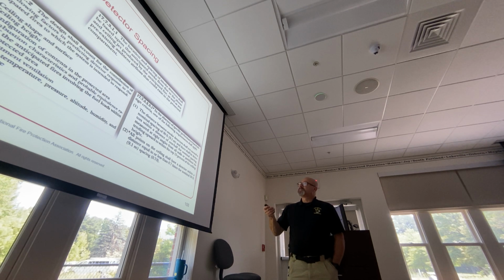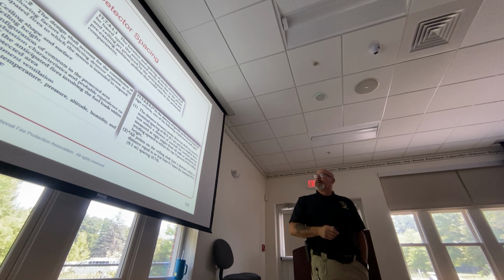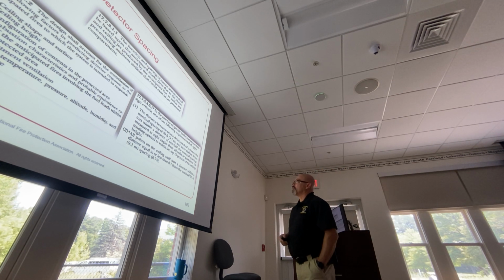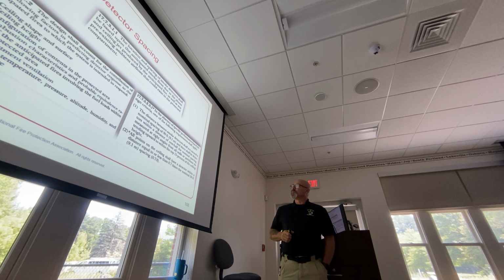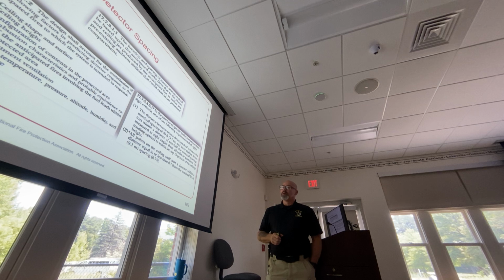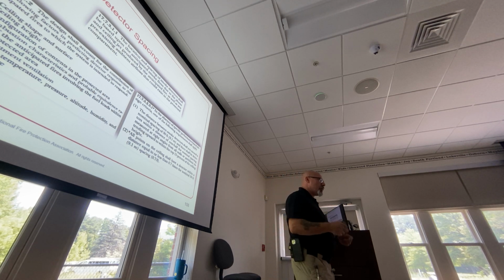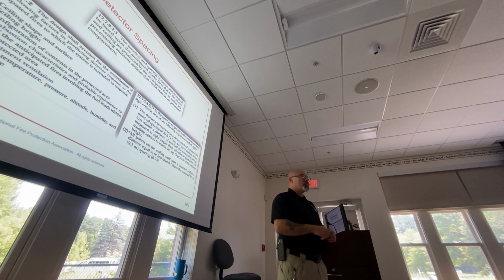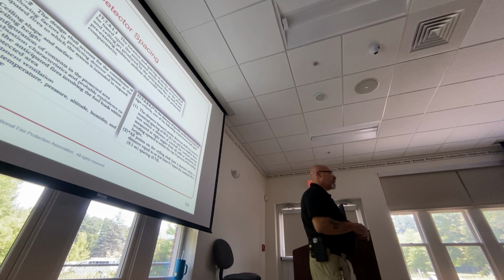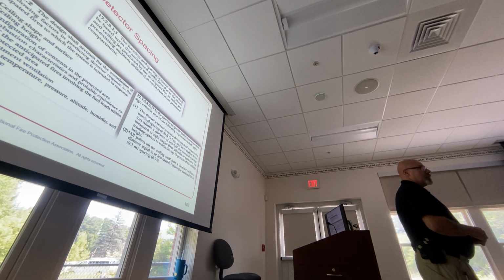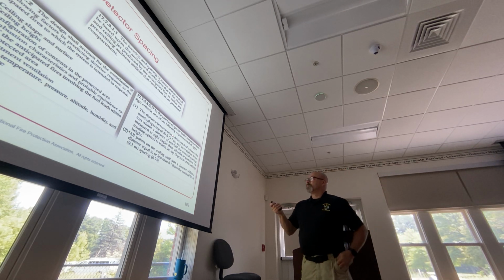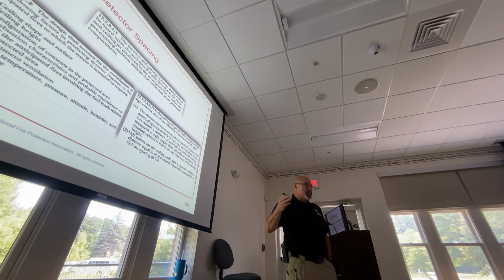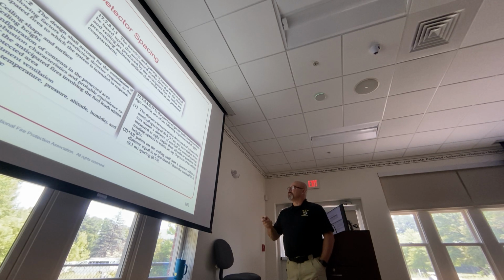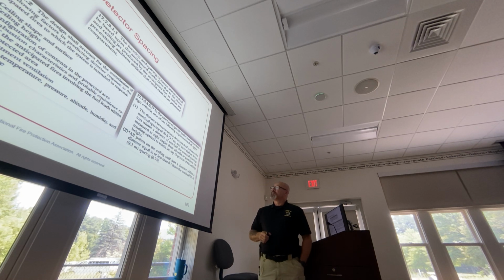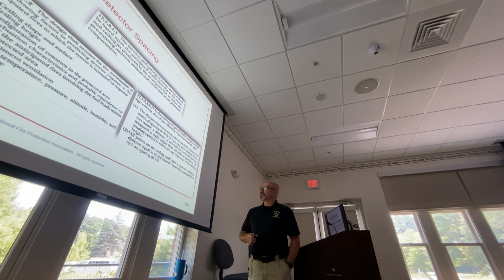All right, so 17.7.3.2.3.1 with an asterisk, meaning there's information in the annex about it. In the absence of specific performance-based design criteria, one of the following requirements shall apply. The distance between smoke detectors shall not exceed a nominal spacing of 30 feet. Most smoke detectors, when you open up the package for them, and of course we're talking about fire alarms here, most detectors are going to give you a specific distance. The manufacturer is going to tell you what their product is good for. In the event that they don't, it shall not exceed 30 feet. There are exceptions to this, but as a general rule, it won't exceed 30 feet, and there shall be detectors within a distance of 1/2 the spacing measured at right angles from all walls, partitions, and so on, extending upwards.